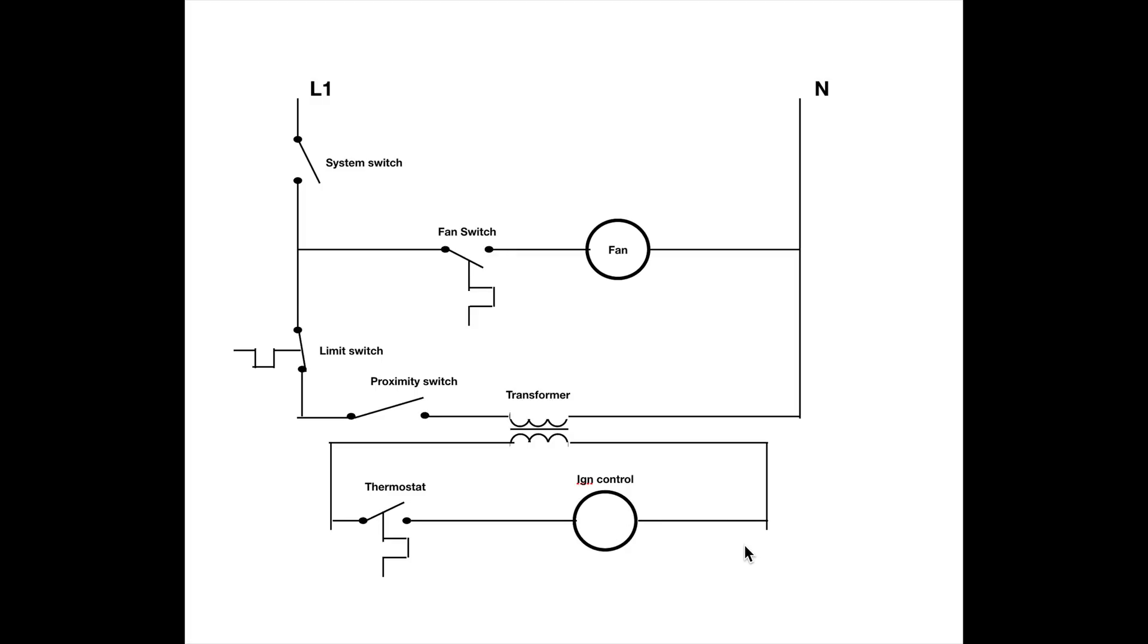That's pretty much the whole ball game but let's look at what happens when I'm out there and the unit starts up. The thermostat will probably already be closed because it's cold out there. So when I walk in, this proximity switch here will make, that powers the transformer and that fires up through the thermostat, the ignition control which starts the burners. Then the burners, as they warm up, this fan switch is going to close and turn on the fan.